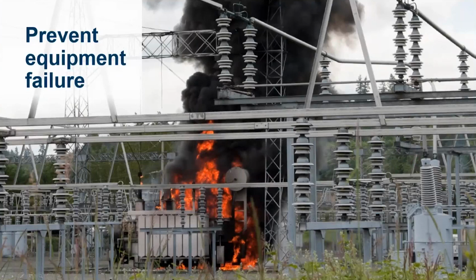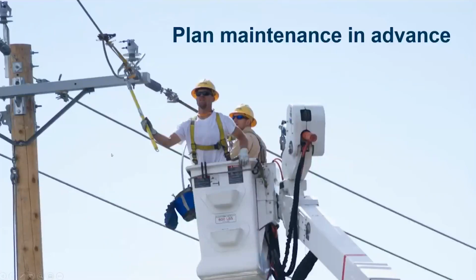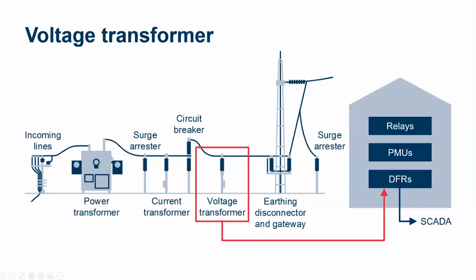And so that leads us to the equipment failure. And of course, this is not what we want. We want to detect before, if possible, any particular failures, so we can plan the maintenance in advance. And today I'm going to specifically talk about a use case, and we wrote a paper with Salt River Project on 2 failures of a PT that they had and how they used this particular data to identify those failures and then make actionable decisions from that. So that paper is on our website, and it's available for download, and we can send you a link as well if you'd like, maybe in the chat.